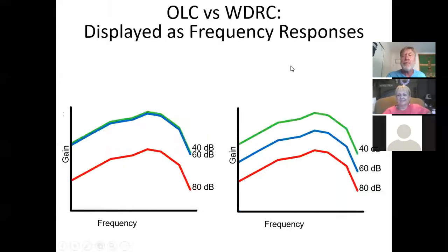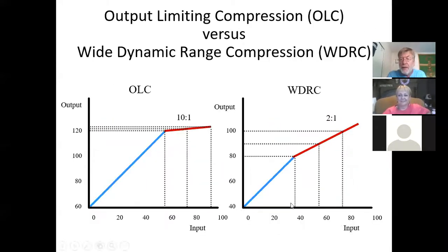Okay, watch what it looks like on an input-output function. Lots of linear gain, but it's a weaker hearing aid. Remember, it's a weaker hearing aid. So 0 in, 40 out, 20 in, 60 out, 40 in, 80 out. So my linear gain, albeit less than over here, but it's linear, but the most gain is being provided for soft inputs.